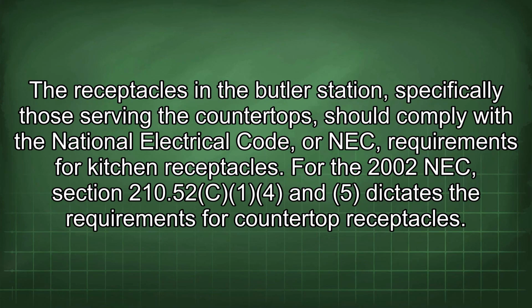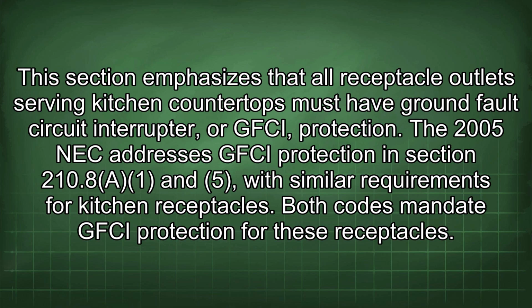The receptacles in the Butler station, specifically those serving the countertops, should comply with the National Electrical Code, or NEC, requirements for kitchen receptacles. For the 2002 NEC, Section 210.52(C)(5) dictates the requirements for countertop receptacles. This section emphasizes that all receptacle outlets serving kitchen countertops must have ground fault circuit interrupter, or GFCI, protection. The 2005 NEC addresses GFCI protection in Section 210.8(A)(5), with similar requirements for kitchen receptacles. Both codes mandate GFCI protection for these receptacles.